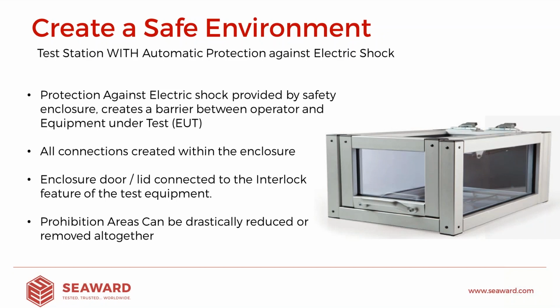It may not always be the most practical because of the size of enclosures, and therefore things like the weight of doors and other health and safety risks that could pose. But it probably would be deemed as being the safest way to perform testing. Most often, the test enclosure itself will be fitted with some sort of interlock system, so that in the event that the door was open during testing, the power to the equipment under test is instantly removed. Commonly, that is done in tandem with the test equipment, and we'll talk about interlock features on test equipment a little bit later.